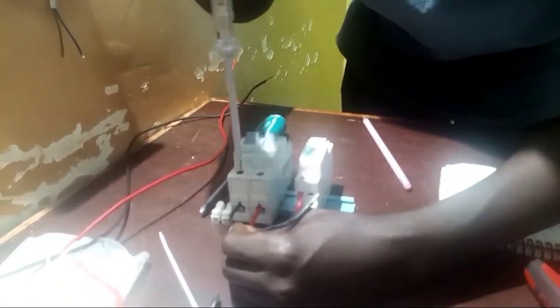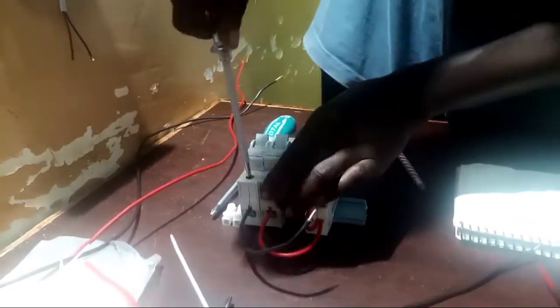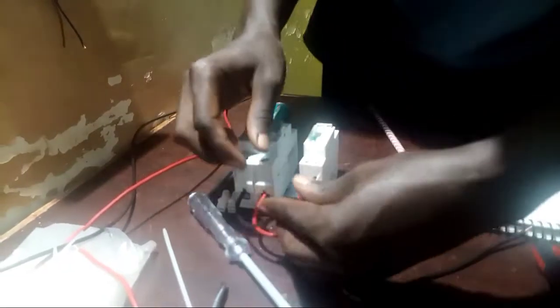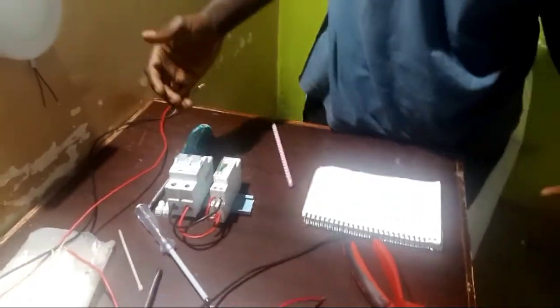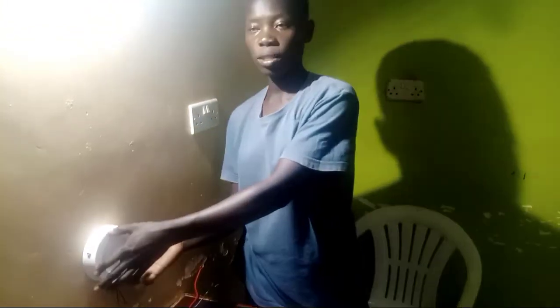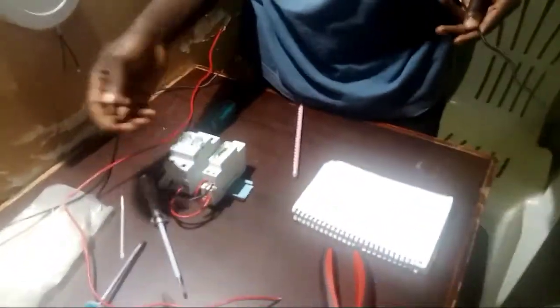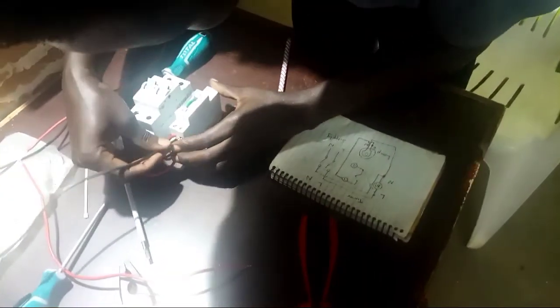So after connecting the power, now we are going to loop the neutral. So the neutral from this end, from the supply, we connect it to N, indicating neutral on the timer. So after that, we need to connect the live and neutral terminals of the load, which is the lamp, as it is mounted here. So we are going to connect our live and neutral. The neutral that we are going to use is coming from the timer connected to the load. So this is the cable that we're going to use.